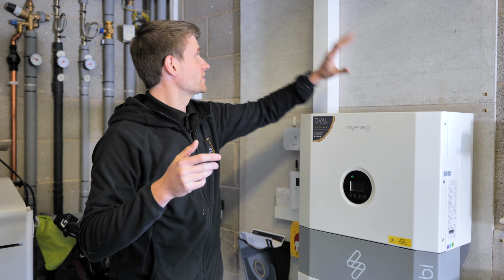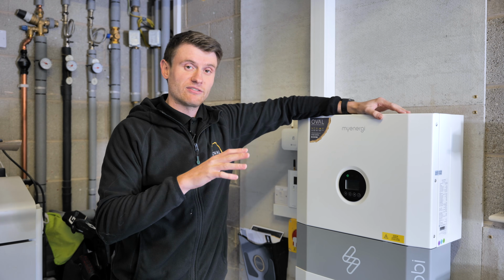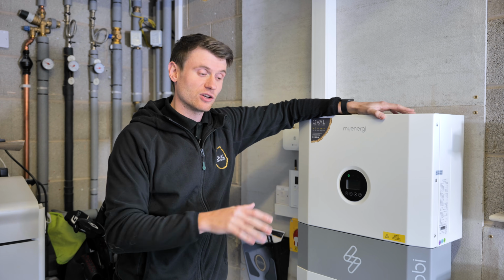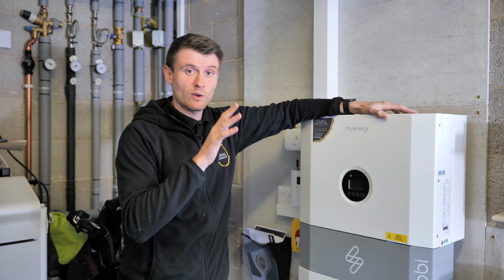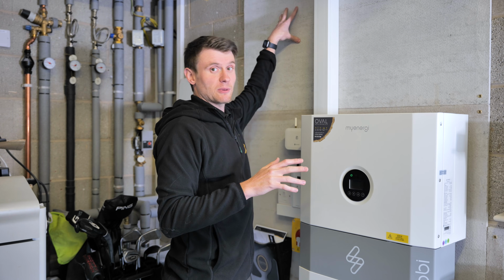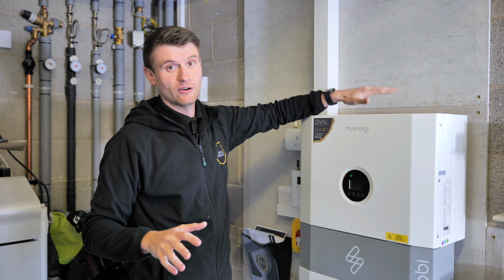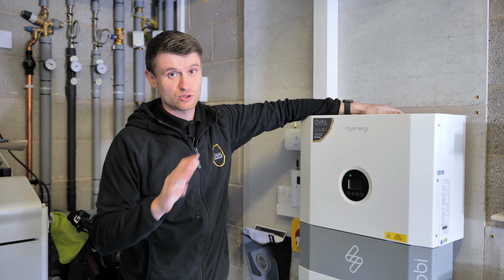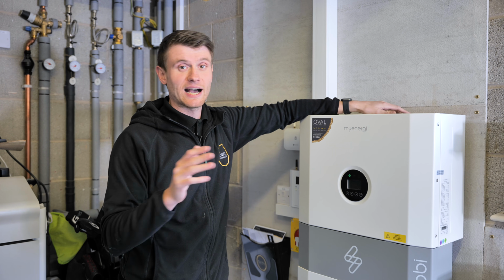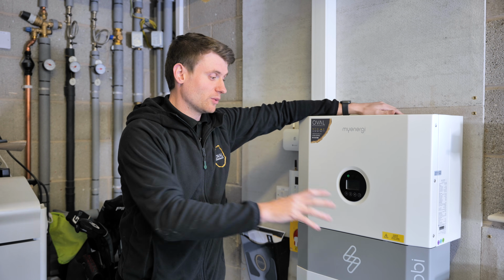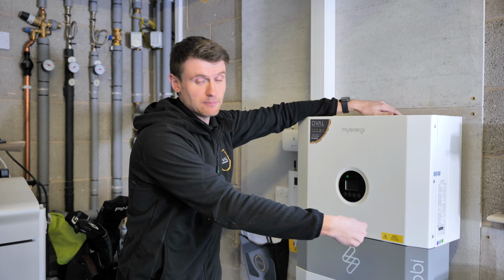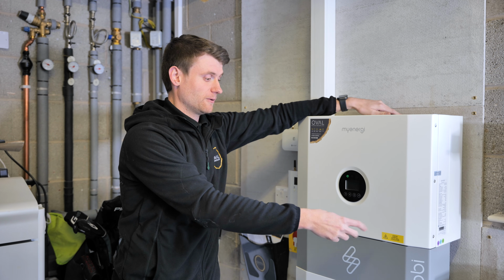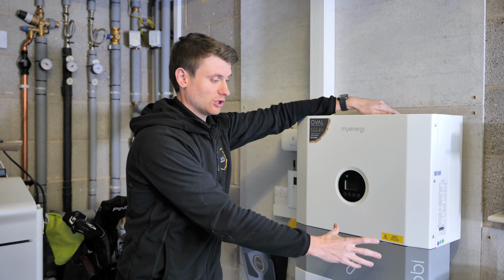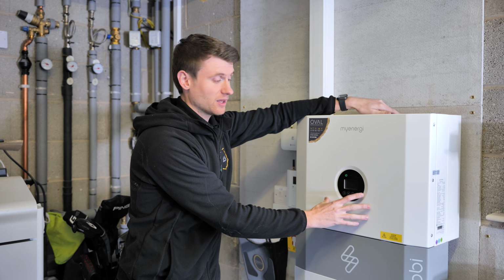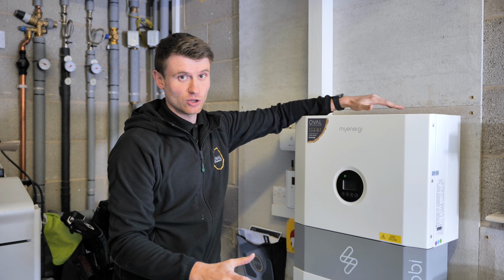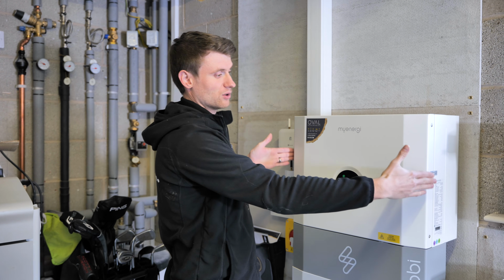I mentioned earlier about this space here, about the customer potentially having another solar PV inverter in the future. If, when we applied for say a 5 kilowatt solar PV inverter, the DNO said unfortunately there's just too much capacity on that, you can't have it, then what we can do is through those DC inputs we saw earlier in the video, we can actually put solar PV directly into this system.